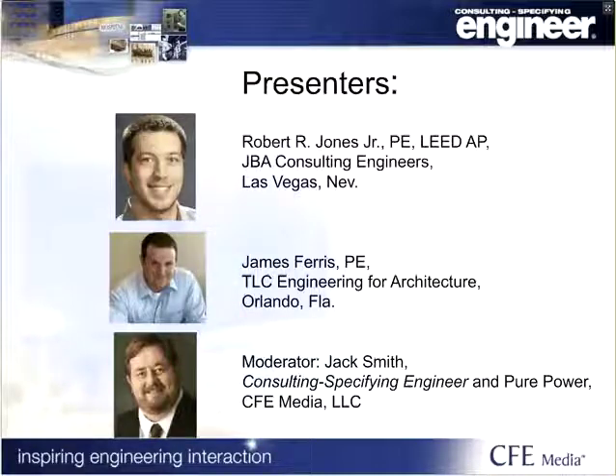Okay, Rob, how about this one? If you are relocating an existing generator from one campus to another, is an NFPA 110 reactive load test required, or can resistive be used? I think that was a Jim slide as well. That's a good question. I would say if it's a newer generator and you have a copy of the reactive load bank test, then that's something you can certainly point to, and there are some provisions in NFPA 110 for redoing your load bank tests and what the criteria are for it, so you could follow that. If you don't have it, then I would certainly require a reactive load bank test for that new installation.